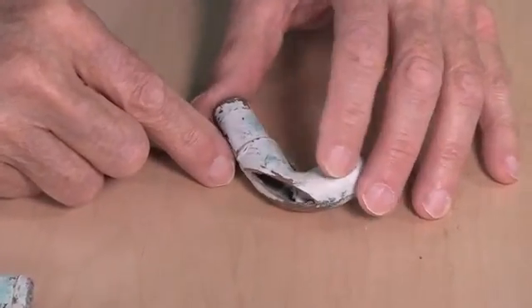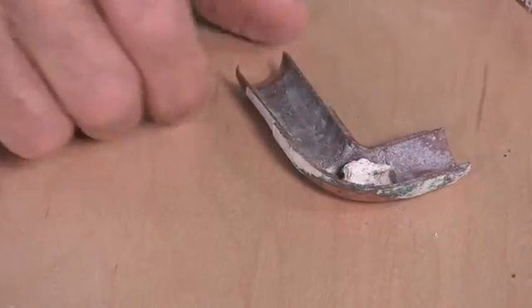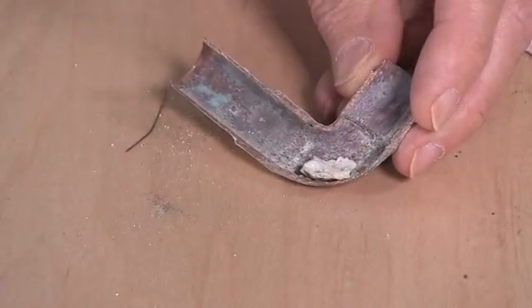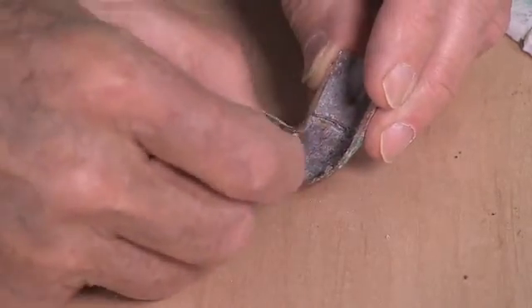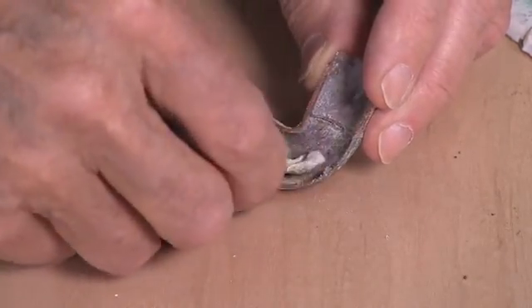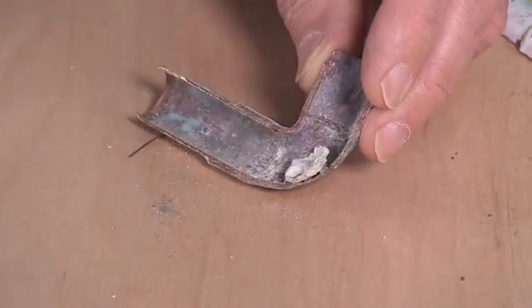I cut this thing open to see what was going on, and then I removed half of it like this. And there were a couple of things down here. First of all, there was this piece sitting in the corner. Great big hunk. There was some other smaller stuff that has disappeared since then, but sitting in there.